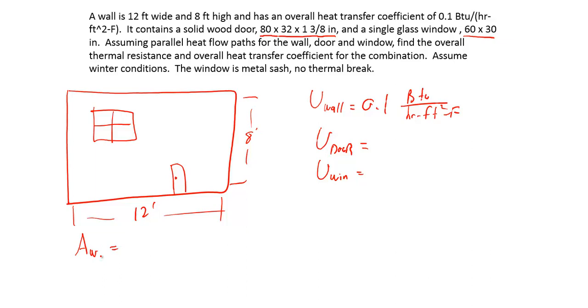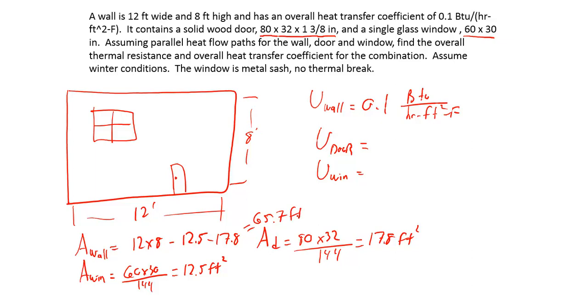We have the area of the wall. It's going to be that 12 by 8 to subtract out the area of the window, which is a 60 by 30 inch window, which equates to 12.5 square feet. We subtract that away from the wall, and we can also get the overall area of the door, which is 32 by 80 vertical inches or 17.8 square feet. So the wall is about 67 square feet, the window is 12.5, and the door is 17.8.